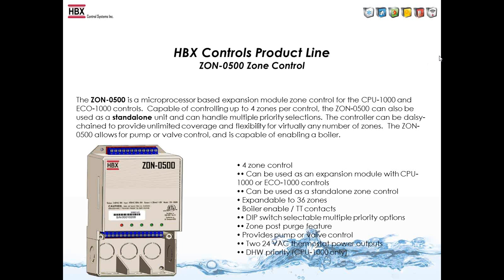Also, if it's connected with the ECO-1000, the heat pump control, you can actually say you want heating zones or cooling zones, and if it's in cold weather shutdown, the heating zones will be locked out, and if it's in warm weather shutdown, the cooling zones will be locked out for zone protection, so you're not sending heating water to your cooling zone and vice versa.